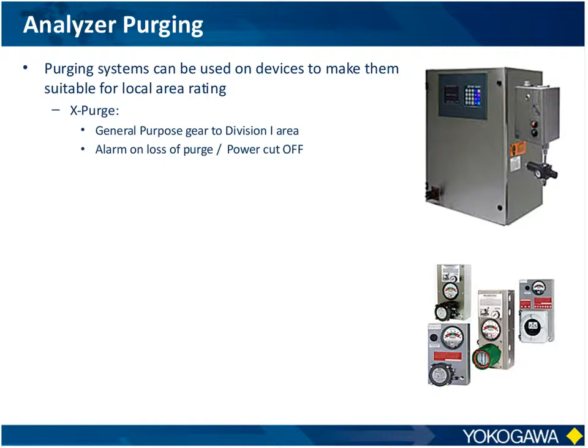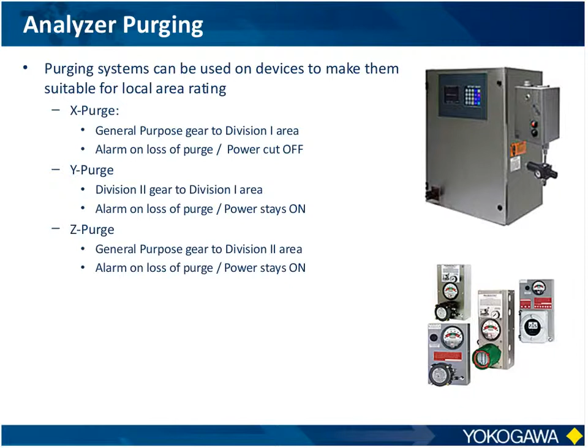You might have what they call X-purges, where I'm just trying to take a general purpose piece of equipment and move it into a Division 1 area. If I have a loss of air because the air system got cut off by accident, I have to turn on an alarm, and then I have to turn off the power to keep a safe environment, because I don't want the analyzer operating now that I've lost my purge. But you also have things like Y purge and Z purge, where I'm allowed to keep the power on because the analyzer itself is perhaps inherently safe. It's just not safe for particular situations.